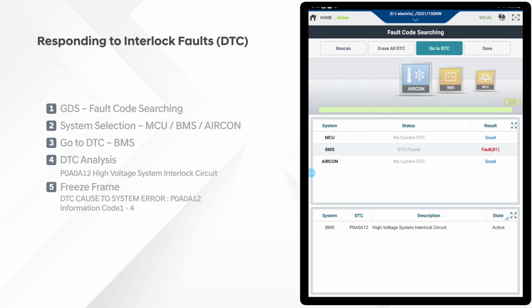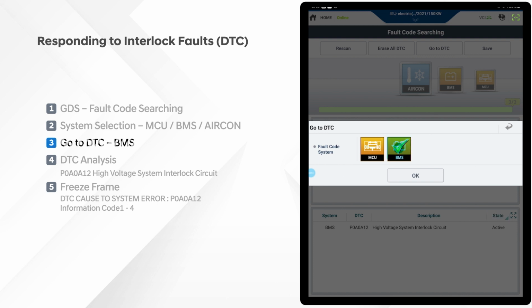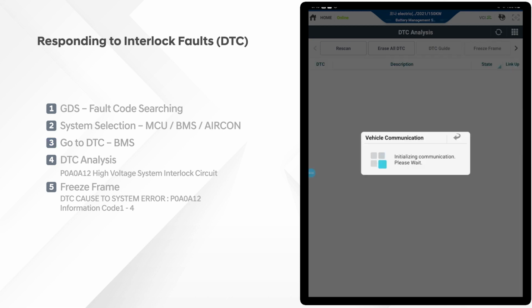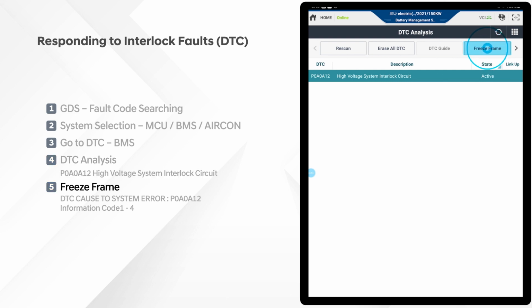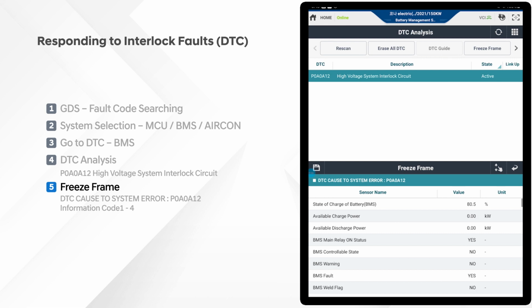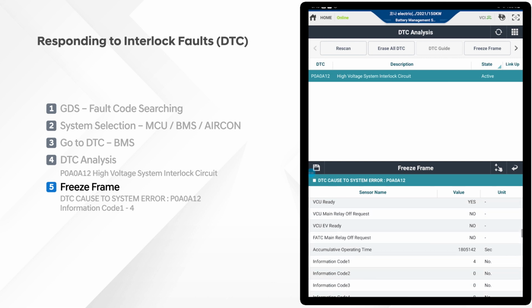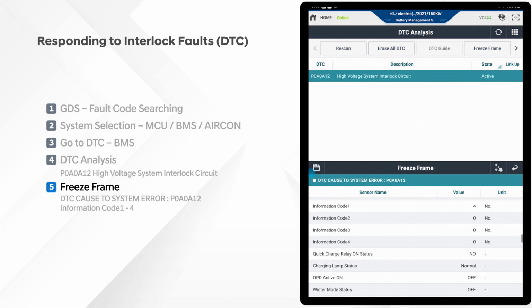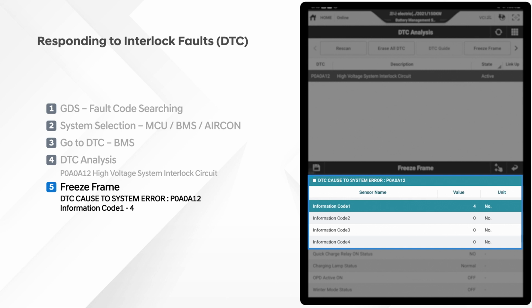As explained earlier, there are 4 channels of interlock detected by the BMU, and the channel with trouble can be found in info code 1 of the DTC freeze frame. Then, let's check the detailed trouble information. Select Go to DTC. Select Freeze Frame. From the info code 1, number 4 is confirmed, indicating trouble in the service interlock. As such, the BMS can identify the specific trouble point using freeze frame information.